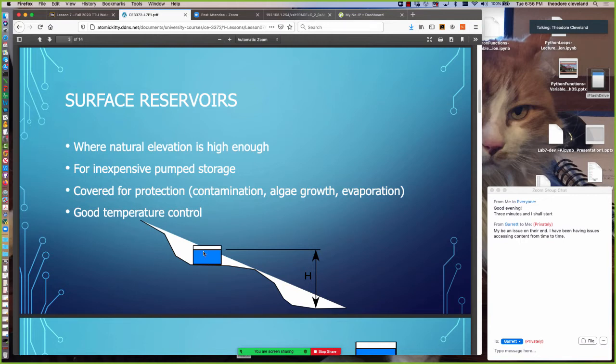And the total head that tank can provide, at least momentarily, is the distance from the regular pool elevation to the demand center elevation. So these are a desirable feature if your particular design situation can support it, meaning you have hills that you can acquire property rights to.